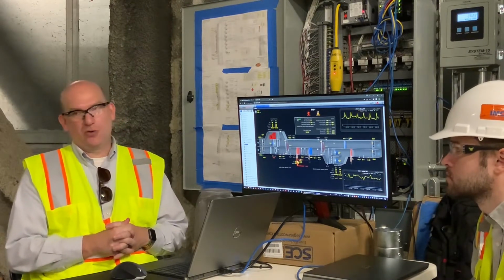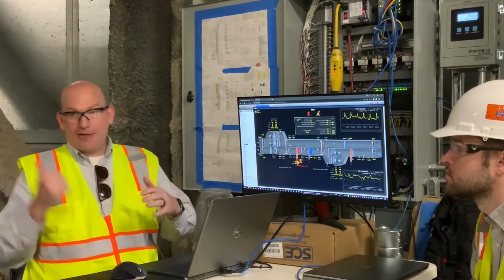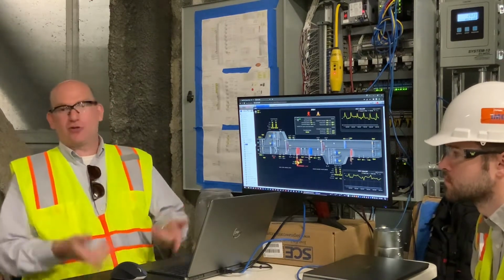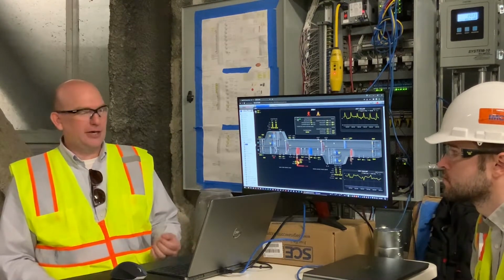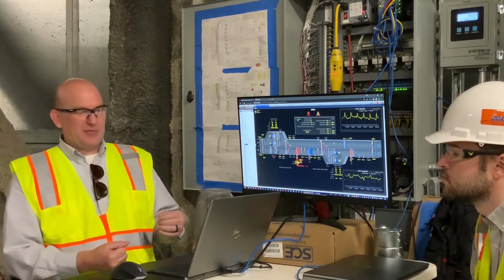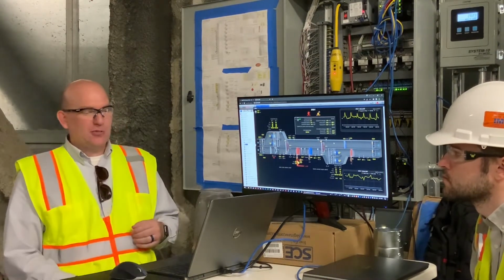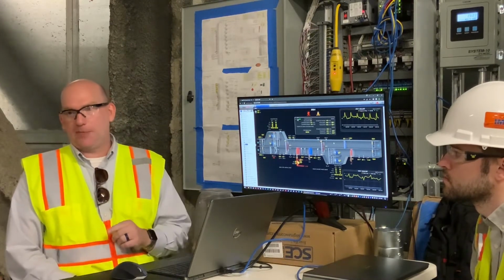Because if we don't, if we just open the dampers and then try to start the fans, and the other units are running, air is going to rush through and spin the fan backwards, and you can fault out the VFD and it definitely won't start. Okay? So what that means, a long way of me saying, if you have to restart one of these air handlers, you should expect to see the fan start before the damper opens.